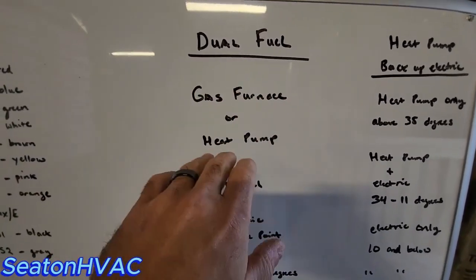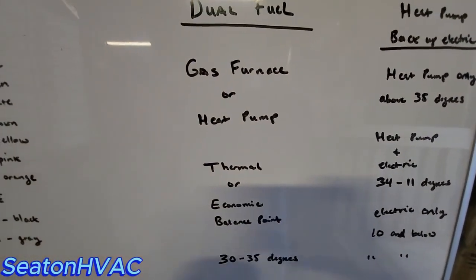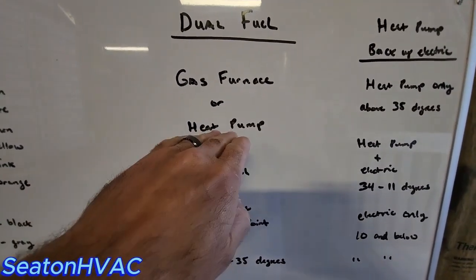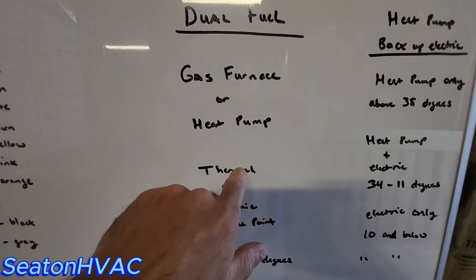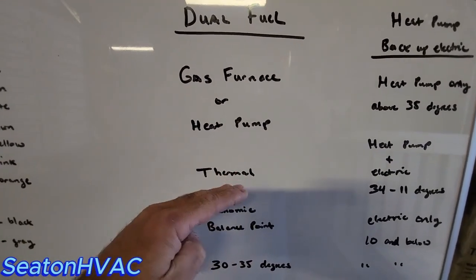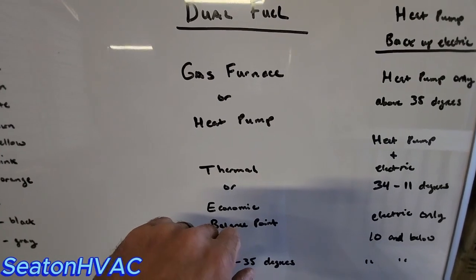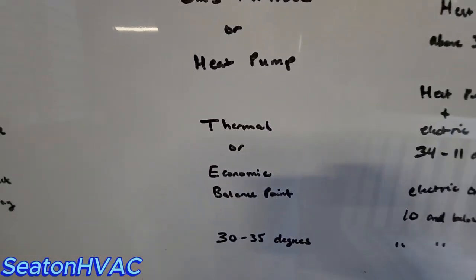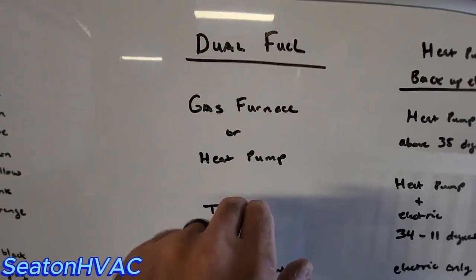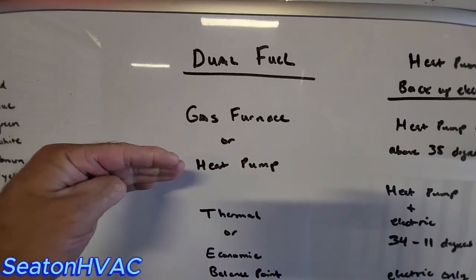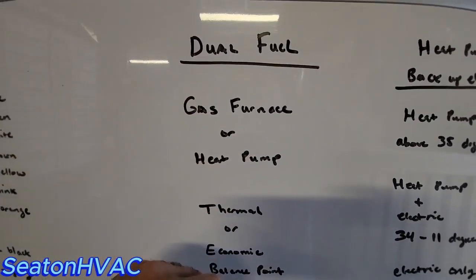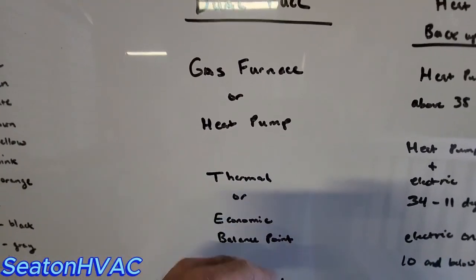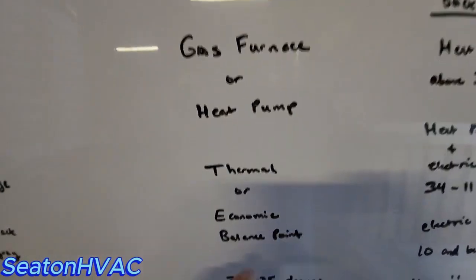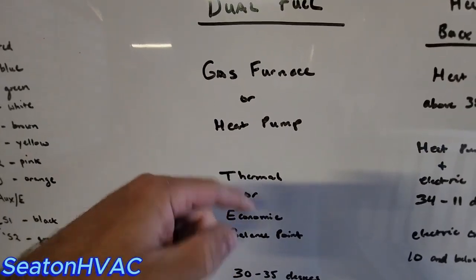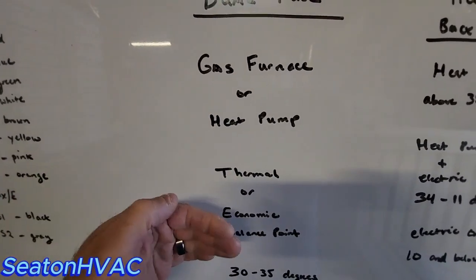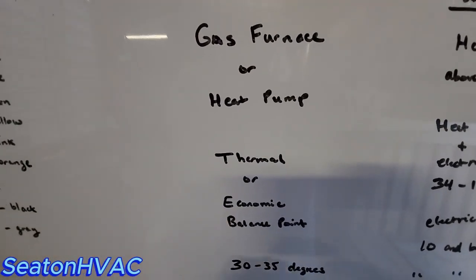How do we determine where that switch over is? A couple different ways, okay? You have what's called your thermal balance point. What's the most efficient method to heat the house at what outdoor temperature? That can be determined by your balance points that you'll find in the manufacturer's data. And then there's also an economic balance point too, which, sorry, I said that wrong. Thermal balance point is which one will do it the most comfortably, okay? So it's a comfort balance point, basically. And then economic is what's the most efficient, what's going to cost you the least to run, okay? So that can be found out by finding out what your utility data are, gas versus electric. And then you can punch in those numbers, and it'll tell you what your economic balance point is.